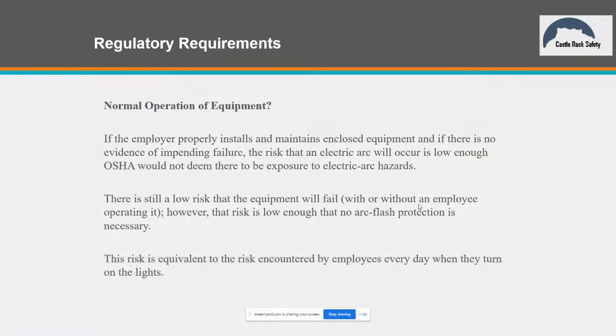They talk about normal operation of equipment. This is something that was adopted in NFPA 70E a couple code cycles ago. They talk about the same thing here in 1910.269. They basically say that if you install and maintain equipment and there's no evidence of impending failure, the risk of electric arc is low, then OSHA says there's no exposure to an arc hazard.